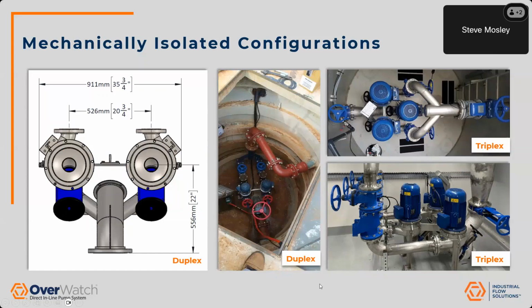As Brad mentioned, we do have many different configurations of these OverWatch available. On the left-hand side, we're showing our duplex configuration with the split discharges. This allows us to put knife gate valves on the suction and discharge side of each volute, which gives us the opportunity to completely isolate one side without having to shut down the complete system. Your second pump can continue to operate, and you can isolate the one volute both mechanically and electrically with a shutoff in the control panel.